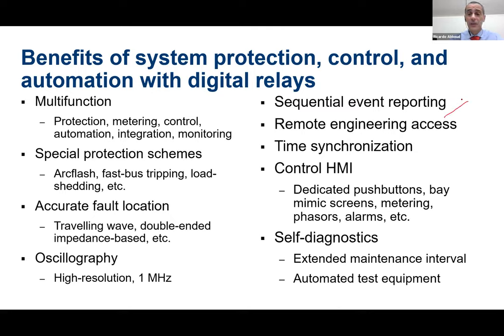With the digital relays, we can do some of the maintenance or also change settings remotely. We can collect data remotely. We don't need to go to the substation. Totally different from the electromechanical relays. We can have all of the relays time synced to a global time source. So this will make it much easier to analyze events or to do a post analysis in the power system. The relays have a control HMI.